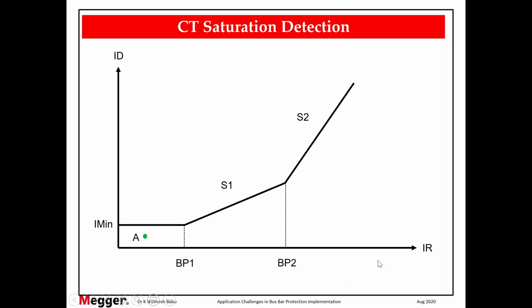Okay. So during this time, what will happen is the point A will slowly increase like this, and it will reach a specific point B. Till this point, no CT has saturated. This is the locus A to B. After it reached B, maybe if your bus bar is having 30 CTs, one CT got saturated, one of the weakest CT. After it got saturated, the differential current will increase further, and it will cross the line and it will appear here. Now, if you see the locus, from B to C it moved.